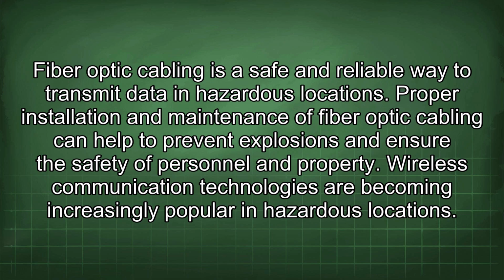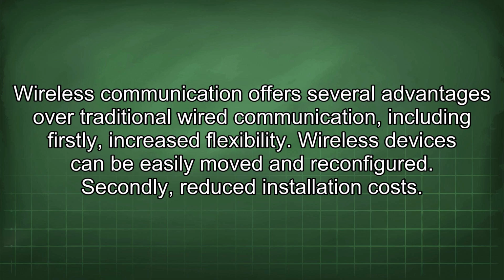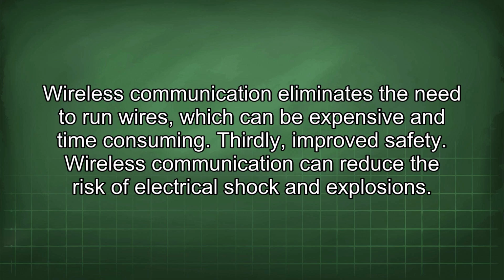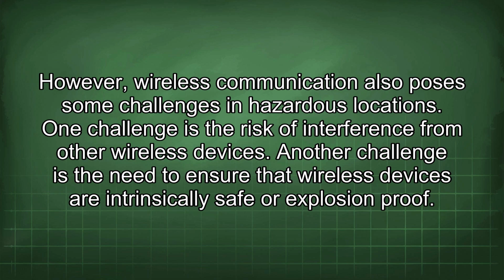Wireless communication technologies are becoming increasingly popular in hazardous locations. Wireless communication offers several advantages over traditional wired communication, including: firstly, increased flexibility. Wireless devices can be easily moved and reconfigured. Secondly, reduced installation costs. Wireless communication eliminates the need to run wires, which can be expensive and time-consuming. Thirdly, improved safety. Wireless communication can reduce the risk of electrical shock and explosions. However, wireless communication also poses some challenges in hazardous locations. One challenge is the risk of interference from other wireless devices. Another challenge is the need to ensure that wireless devices are intrinsically safe or explosion-proof.